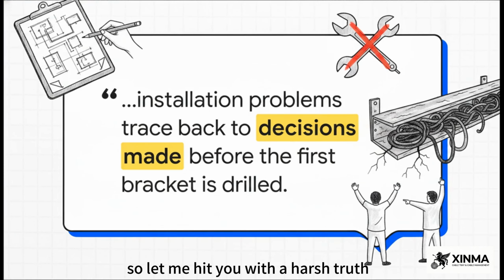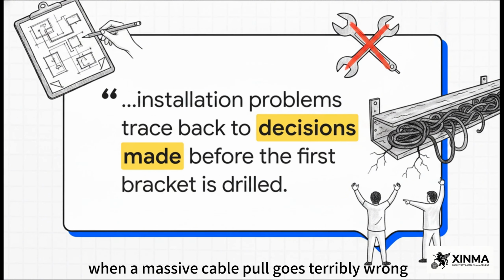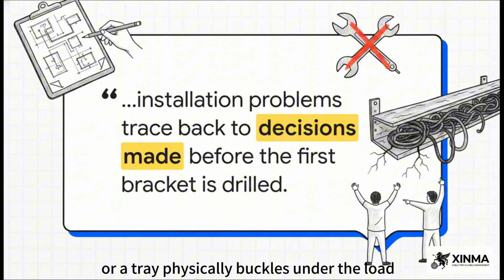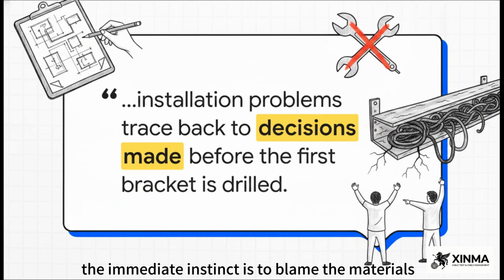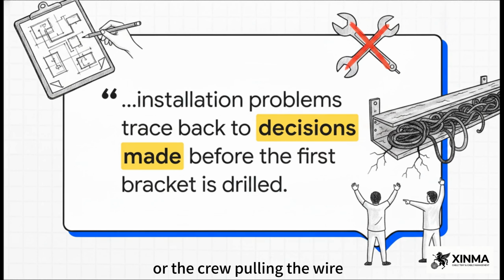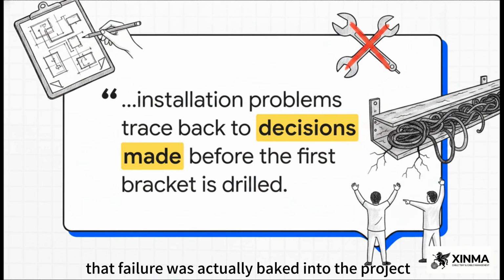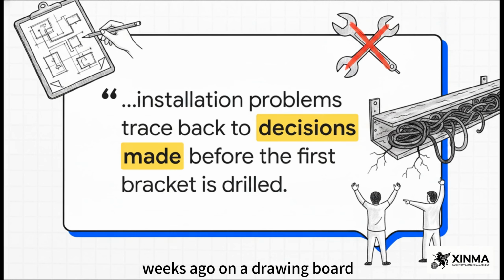So, let me hit you with a harsh truth, straight from the field. Most cable tray installation problems trace back to decisions made before the first bracket is drilled. When a massive cable pull goes terribly wrong, or a tray physically buckles under the load, the immediate instinct is to blame the materials, or the crew pulling the wire. But the veterans? They know the truth. That failure was actually baked into the project weeks ago on a drawing board. The stakes here are incredibly high, because structural failures are dangerous, and reworks will absolutely tank your budget.